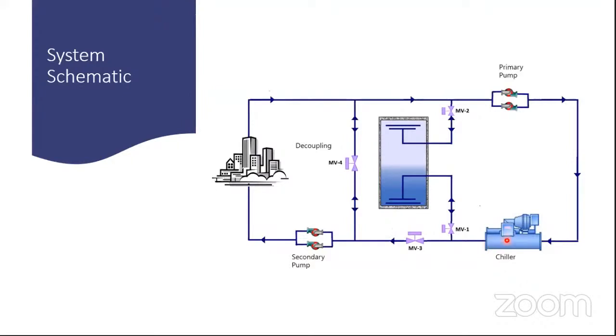One is chiller only cooling. When the chiller is only cooling and thermal storage is not required, these valves stay closed and this one opens. Corresponding to the load, the chilled water is drawn down to the load, and if at all any excess flow is coming from the chiller, it is then bypassed here. So that is chiller only cooling.